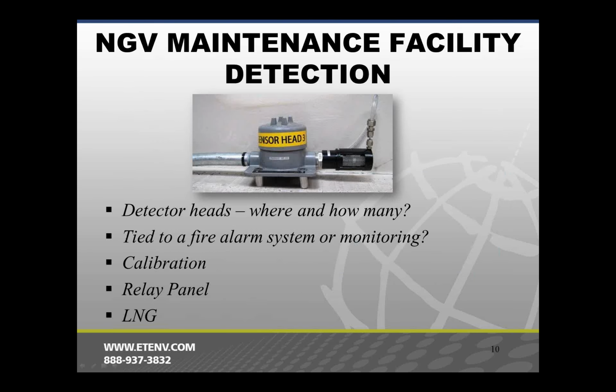Next topic is detection. And we know a lot of times we use it in northern climates to control the ventilation, but what's not specifically talked about in the codes is how many of these things do you need and where do you put them? Well, you want them at the ceiling, because that's where you want to detect your gas, as close as you can to the ceiling. And then, depending on who you ask, you get very, very wide-ranging answers on how many detectors you need. We know that natural gas disperses fairly rapidly. And the short answer is you want detectors that could detect a leak anywhere in your shop. If you were going to have vehicles in any positions where you could have a CNG vehicle, you ought to be able to detect a leak in a timely manner.